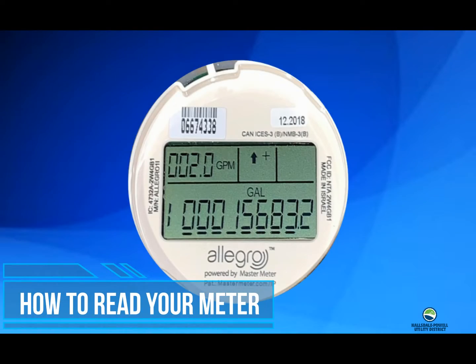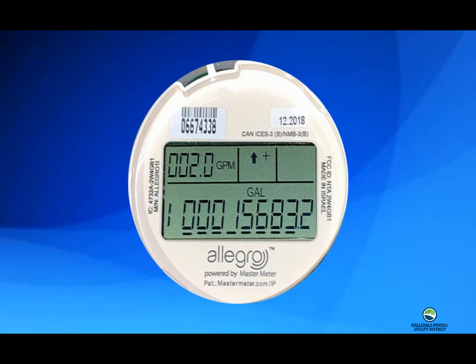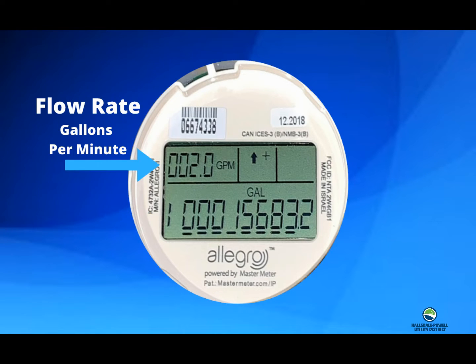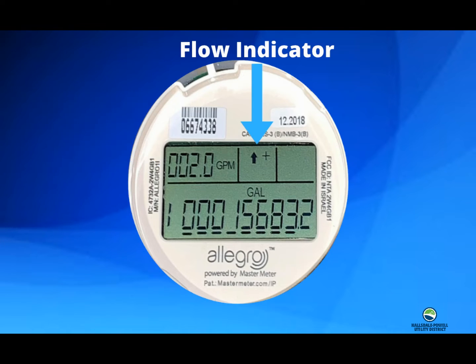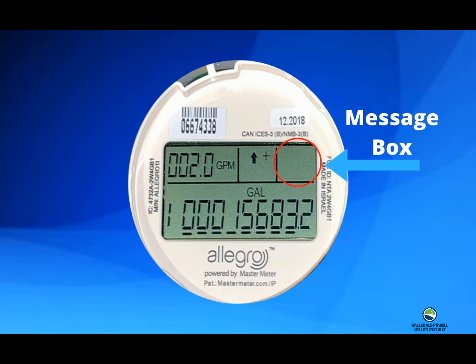The meter you see here is an automated meter that reads water usage in gallons recorded here on the digital display. Most meters are read by a series of antennas, towers, and repeaters that collect transmissions of the meter readings. The top left box shows the flow rate, which is measured in gallons per minute. The middle box shows which direction water is flowing. This is called the flow indicator. The last box is the message box. If water runs through the meter continuously for a 24-hour period, a water droplet symbol will appear in this box.